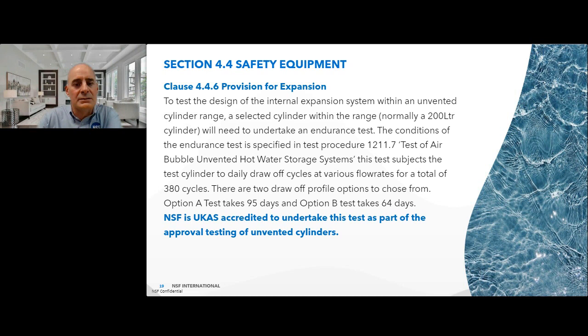This test subjects the test cylinder to daily draw-off cycles at various flow rates for a total of 380 cycles. There are 2 draw-off profile options to choose from. Option A test takes 95 days and option B test takes 64 days. NSF is UKAS accredited to undertake this test as part of the approval testing of unvented cylinders.